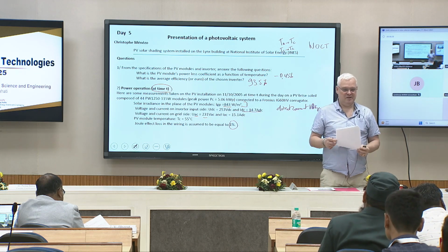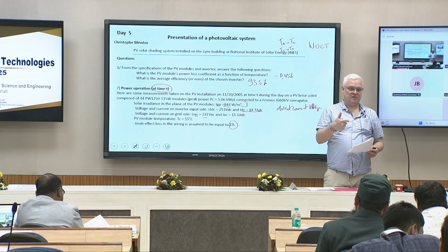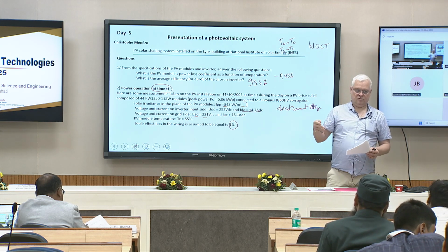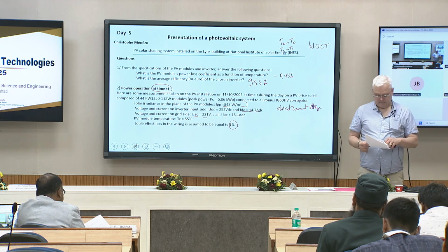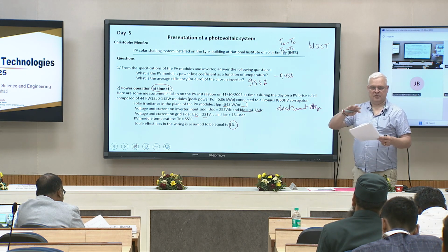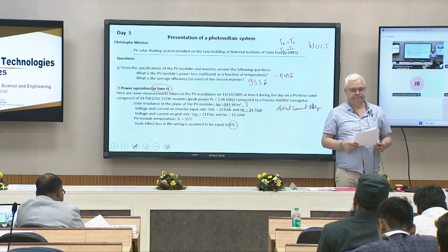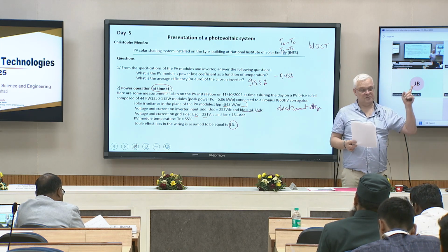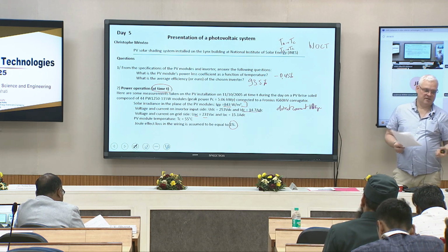So unfortunately, you are obliged to cool this chamber where you put the inverter, the battery. It's better for the lifetime of these components. So usually in very hot countries, they are put in a small house, in a small chamber, which is cooled. So part of the energy produced by the PV central is used to cool the electronic devices.